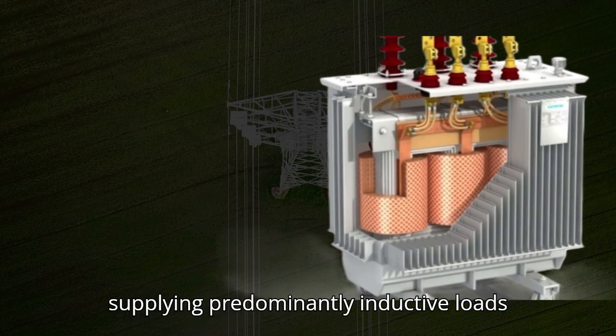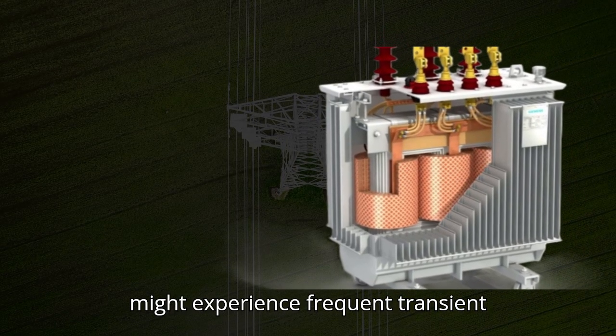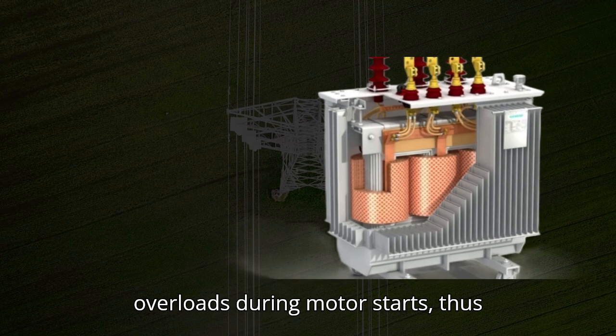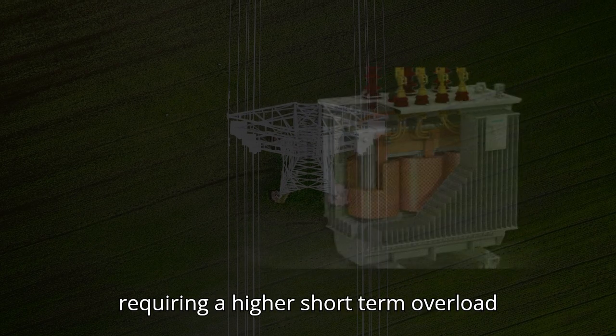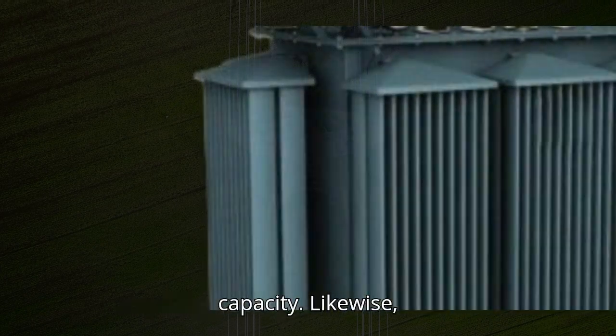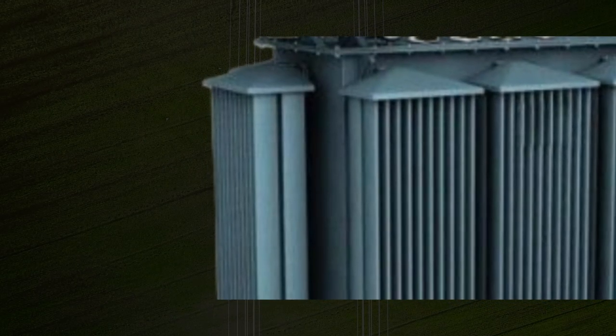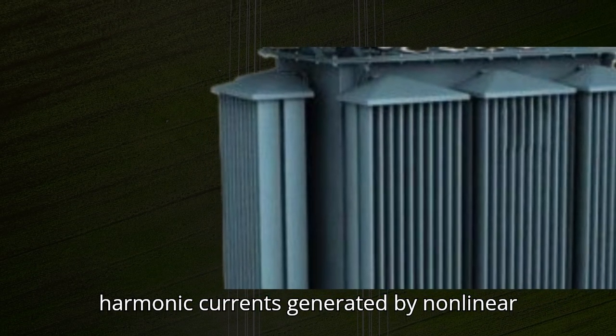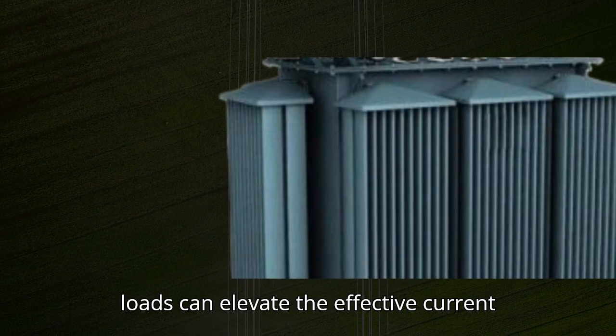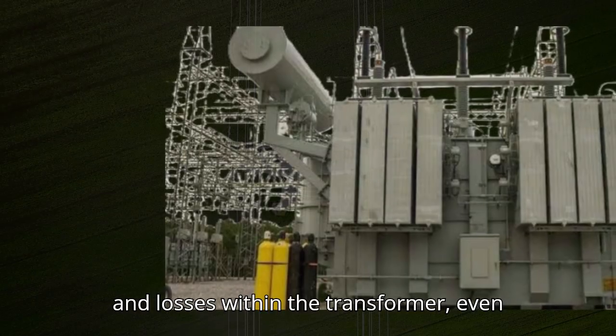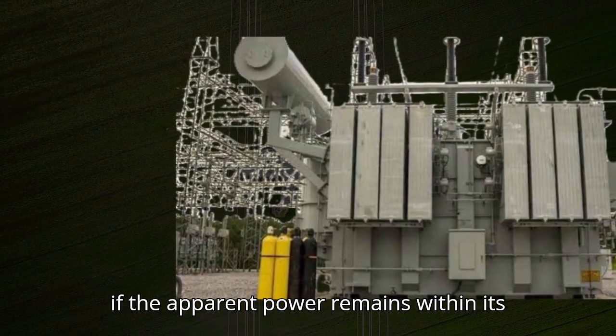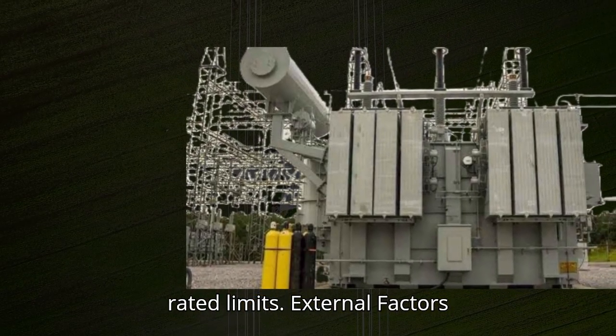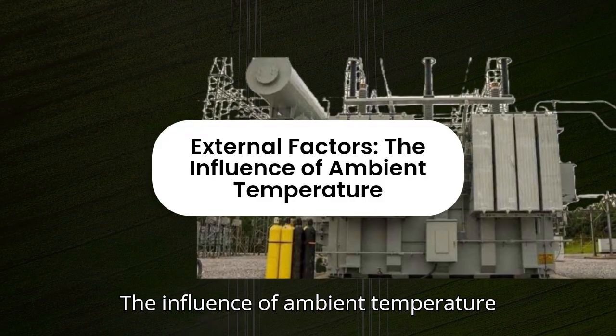A transformer supplying predominantly inductive loads might experience frequent transient overloads during motor starts, thus requiring a higher short-term overload capacity. Likewise, harmonic currents generated by nonlinear loads can elevate the effective current and losses within the transformer, even if the apparent power remains within its rated limits.